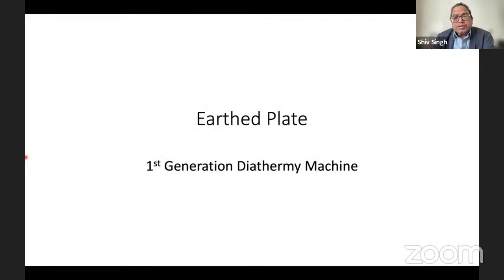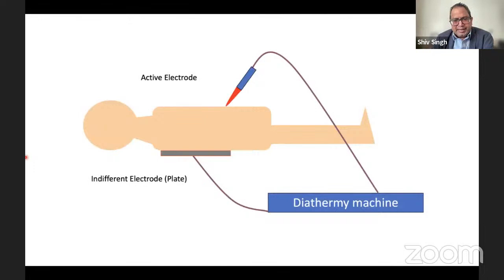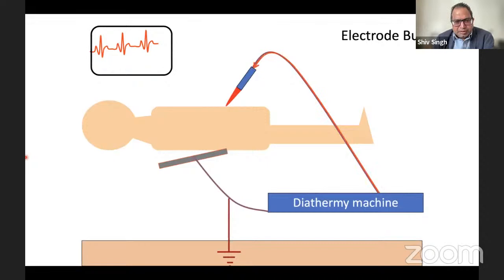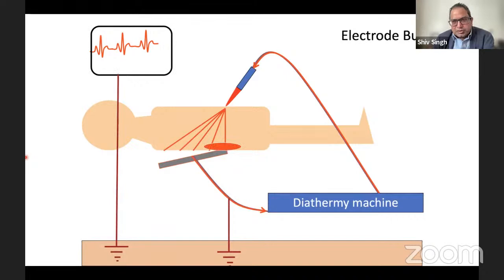So the first generation diathermy plates: if you had a diathermy machine which just had a plate and an electrode, and there was no earthing, then if the plate came off, it won't work. But if it is partially touching, then the density of current will be the same as at the tip, and you get diathermy burns. So diathermy burns were very common when we had the earth plate. That's how it works. Current flows through the plate. So the problem is, if there is partial attachment, you can get higher density current at that point, and it can cause plate burns.